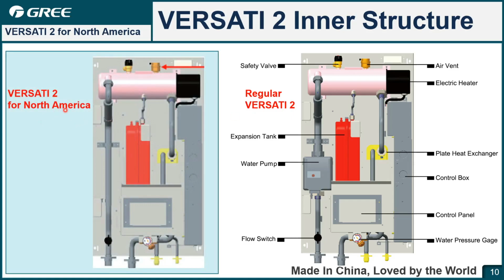However, for North America, you can see the comparison is very apparent, right? Most of the components are the same, such as the pressure gauge, PHE, heater, air discharge, safety valve. All of them are the same. However, you can see for this part, there is no water pump. For North America VERSATI 2, there is no water pump, which means you have to install it in the field, prepared by your customer. So actually this is the only difference between North America VERSATI 2 and the regular VERSATI 2. That's the VERSATI 2 inner structure difference.